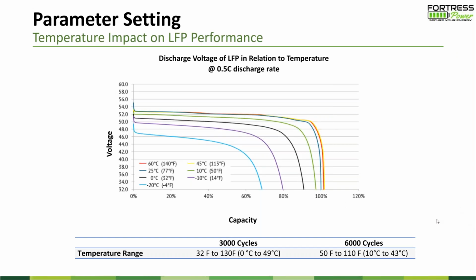So we also talk about the temperature impact. We always recommend 77 Fahrenheit or 25 degrees. That's the best scenario for the batteries. It's cool enough but not warm enough, which is better for the chemistry. And per our instructions, it works all the way up to 43. If you have a special temperature situation, we always recommend that you have a venting system, at least so the ambient temperature doesn't get too high. You see the deterioration of capacity is significant because of voltage. Charging a battery at low temperature is strictly forbidden for lithium batteries. So we don't charge under 0 degrees or 32 Fahrenheit. Anything beyond that, we have to consider the special situation. But with a normal room temperature, from like 5 degrees, 10 degrees, all the way up to 40 degrees, it shouldn't be a big concern.